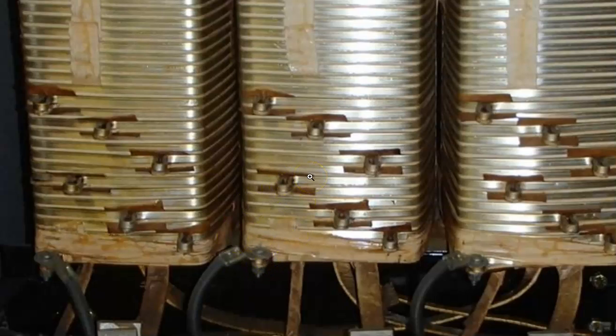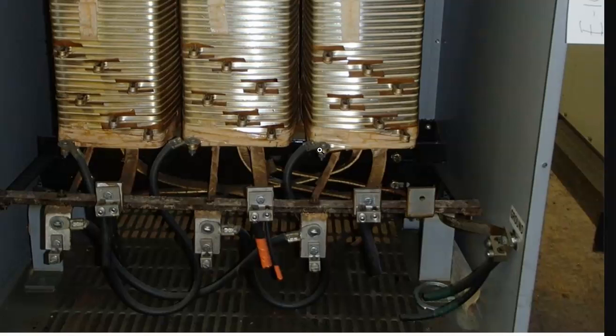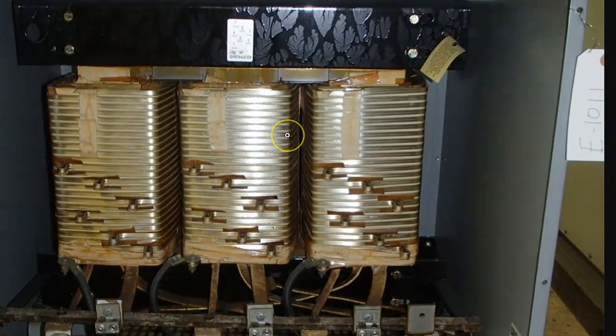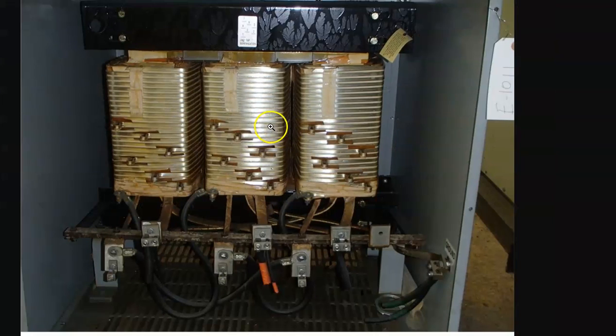This is obviously going to be beyond the scope of most of our millwrights—it's something the electricians should be doing, or you as the plant electrician. If you're doing this, it's going to be, once again, time-consuming. The other thing is, when you open these up, a lot of our transformers are wound with aluminum because it's lighter and a good conductor. Nothing wrong with it, but if we're winding with aluminum, we need to protect it as well—we have to put on antioxidant and things like that.